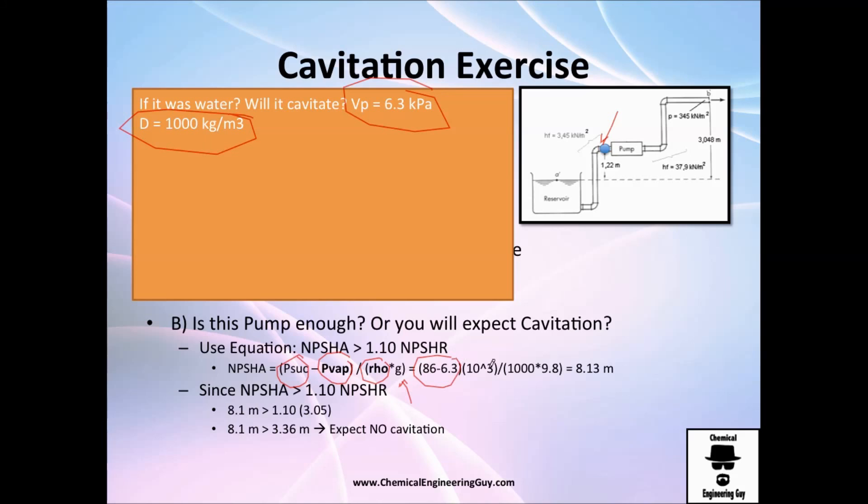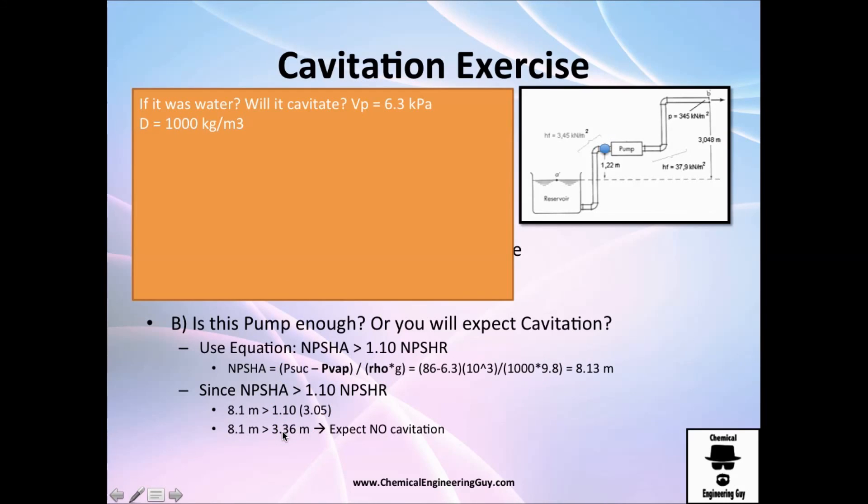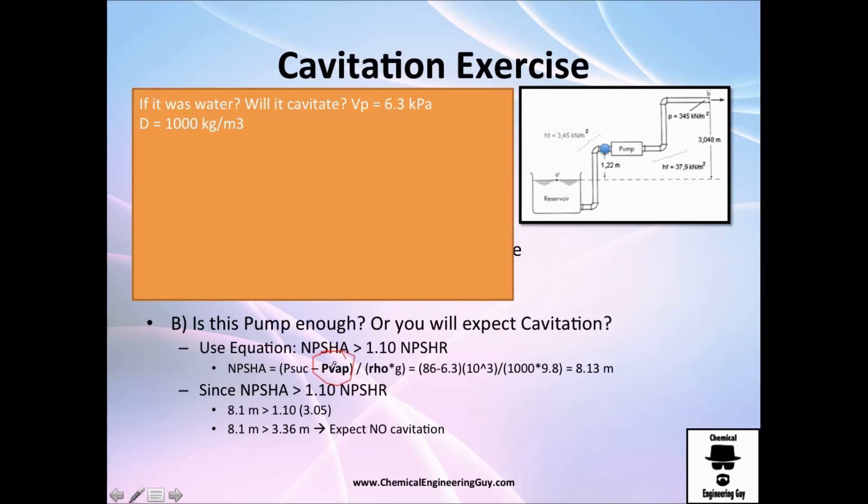So I do this calculation, then 1000 divided by this, and I got this NPSH available. I compare it once again with the 10% of safety, and I see that actually I got more: 8.1 versus 3.36. From the last example was 7.5, so yes, I am still able to work with this fluid. And it makes sense guys, because the vapor pressure is too low compared to this one right here, which was 21. The lower you go, you can see the lower you have this vapor pressure, the more NPSH available you will have. And that's always a good thing to have.